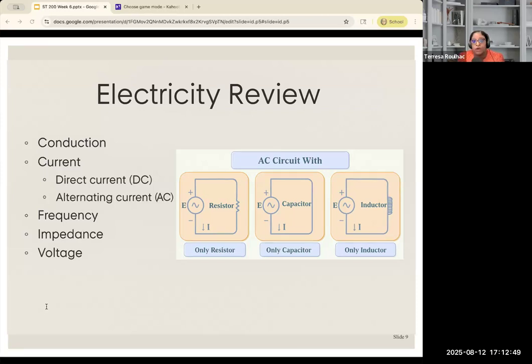The last term that you really want to make sure you have a good understanding of is voltage. Voltage is the force that pushes the current through a conductor. It's measured in volts. It's like the pressure of water moving through the pipes. Okay, so we already have the pipes, and it's how fast it's going. Voltage helps control the amount of current used in electrosurgery. The correct voltage is going to be needed to safely perform tasks like cutting and coagulation.